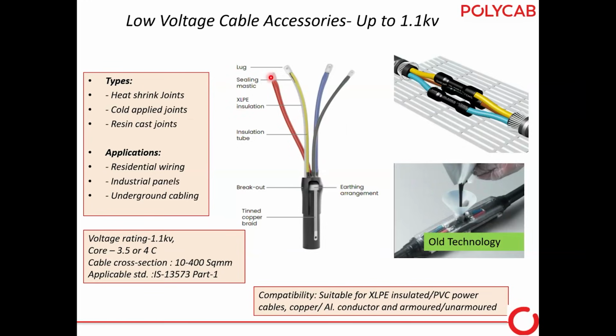So let's see the termination. I will show you how the termination happens. So this is the lug. Over the lug, we apply the XLPE insulation. We provide the mastic here. That mastic is for sealing, so water should not get in from this point. That's why. We provide a breakout, we give an earthing element, and tinned copper braid is provided. So this is a termination.